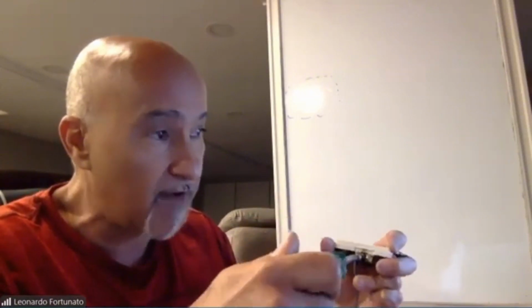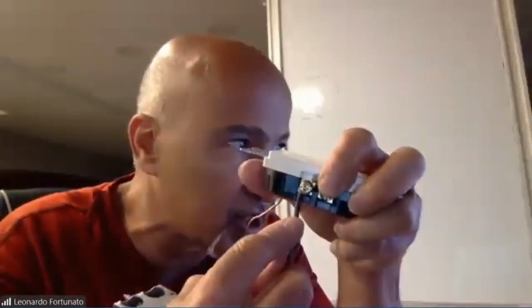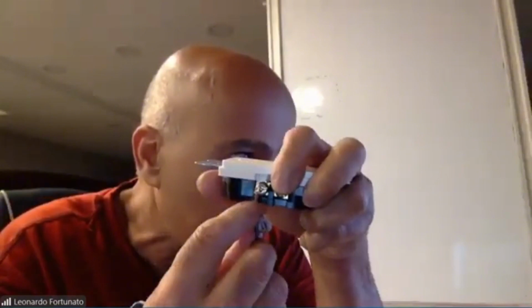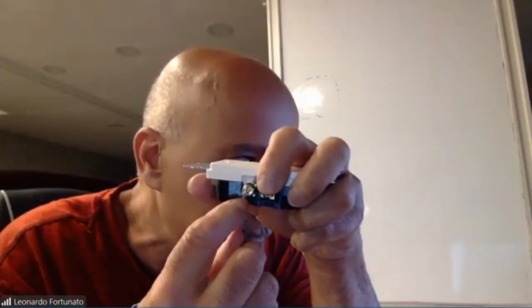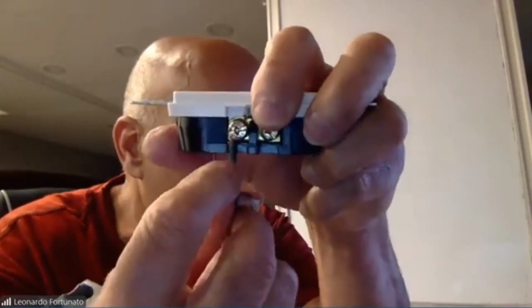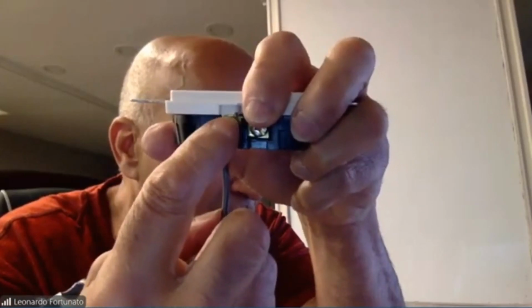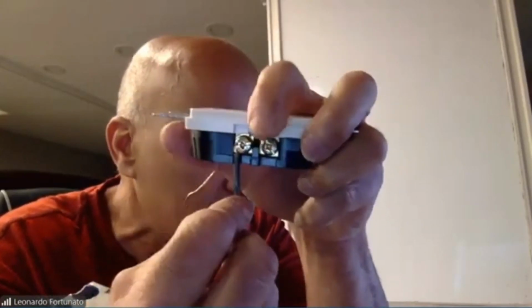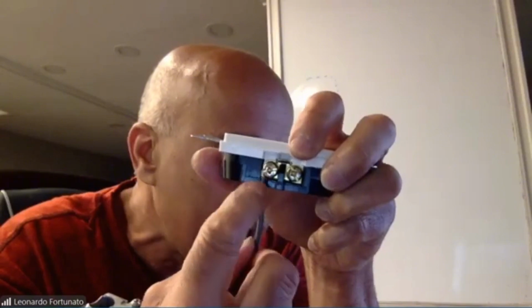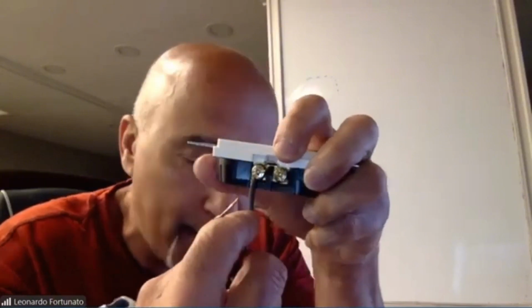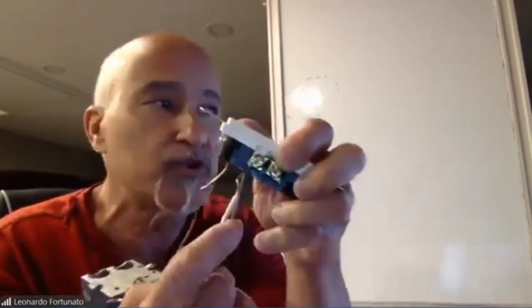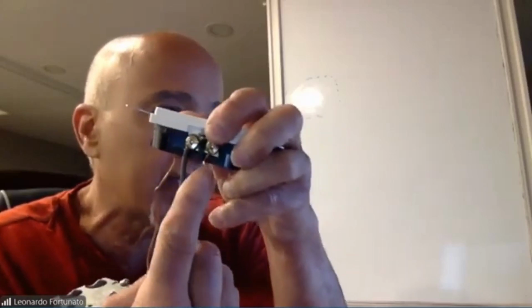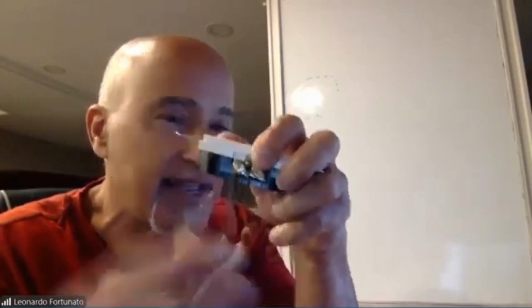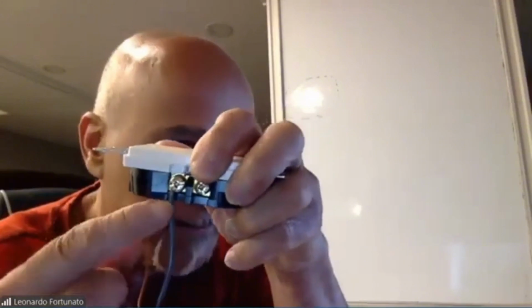I want to show you another important step. When you strip the sheathing off the wire, make sure you have a good joint. We don't want the sheathing going underneath the screw with the conductor, because then you won't make good contact. We also don't want too much wire sticking out below or a big gap. That's a good connection right there, protected nicely.